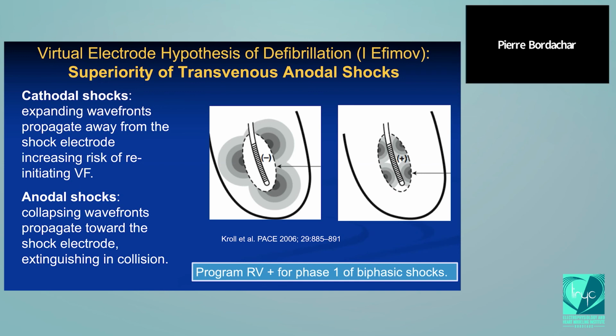Okay. And so if I understand well, for a Boston or Biotronik, you will reverse to anodal shock, if I understand. Correct.